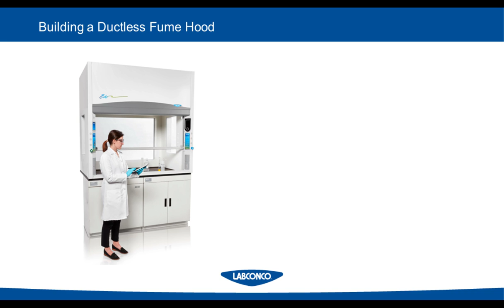But I want to talk about the process of going about getting a ductless fume hood. The first step that needs to be done is an LPQ, or chemical assessment, needs to be filled out. As I have mentioned and as Ken has mentioned, this is a very important step because it determines the filtration compatibility and the requirements. There are certain things that we can add to the filtration column that can maybe handle a certain part of your application, and ultimately make sure that the longevity of these filters and the safety of the operator are ensured.